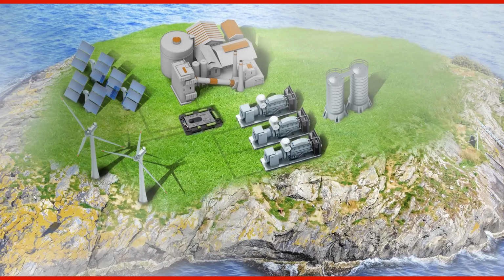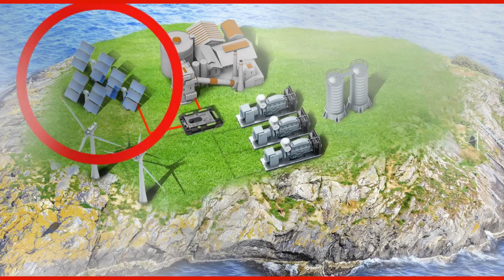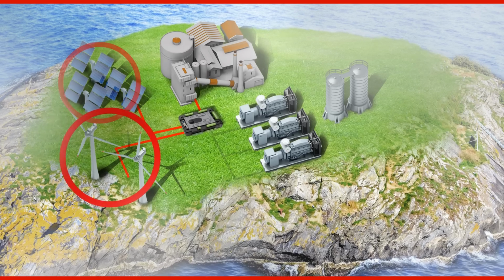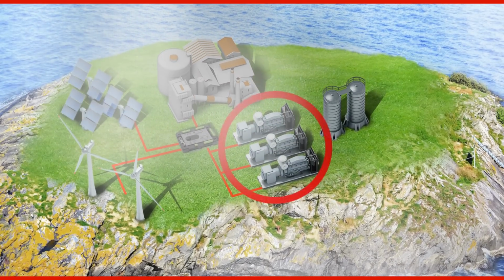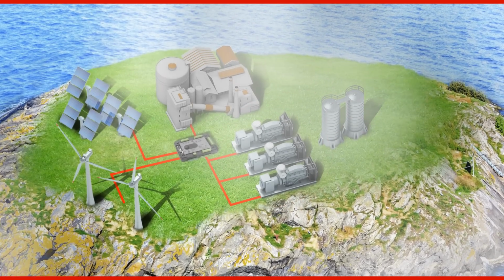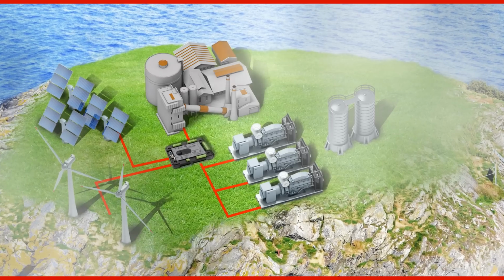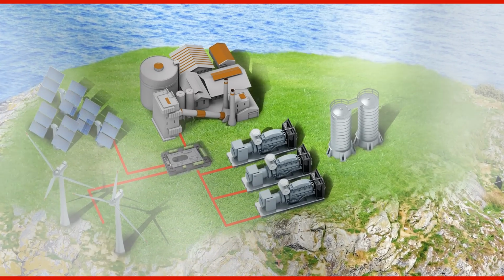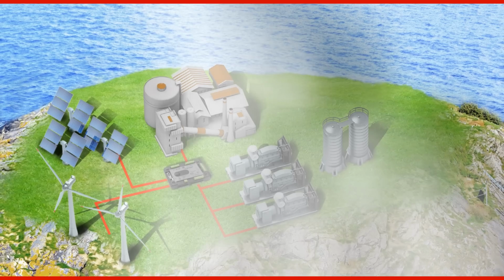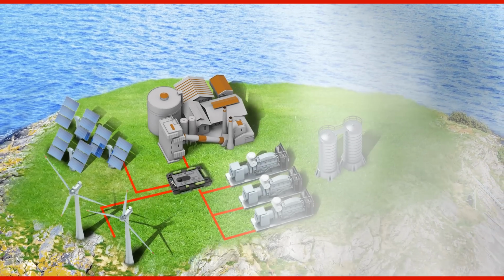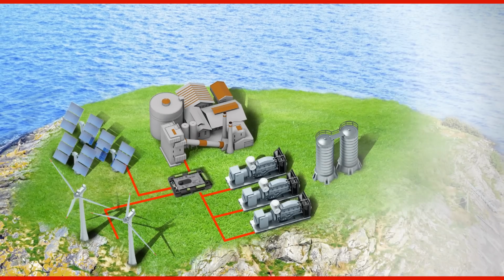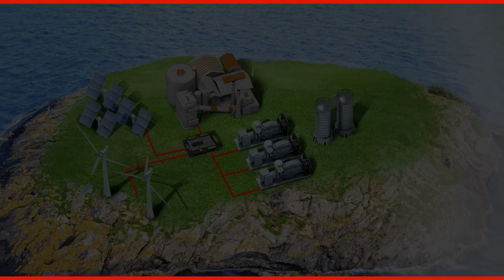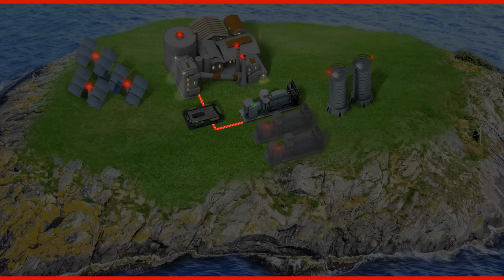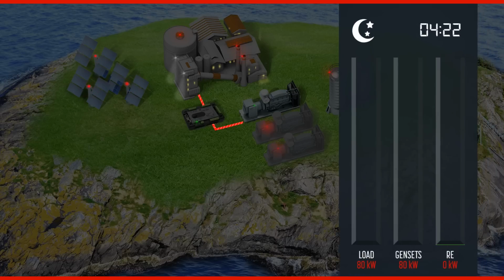ComAp's hybrid system works by continuously monitoring data from all sources of energy, including solar, wind, or hydro, and gensets. Should the energy production from the source of renewable energy drop below a certain threshold, ComAp's controller automatically starts a backup diesel generator to ensure the continuation of power. The ComAp controller automatically starts, synchronizes, and loads the genset to run smoothly alongside the renewable source. When the energy production from the renewable source becomes feasible again, the system automatically switches to the renewable source and cycles down the generator.